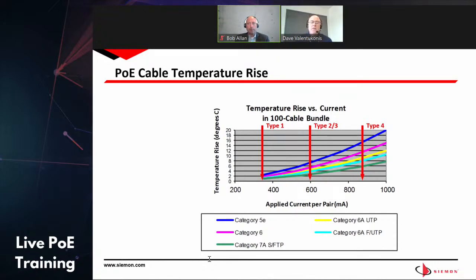Category 5E, for example, is less tolerant of heat because it simply has smaller conductors than the others. As you go up the ladder to category 6, category 6A, category 6A shielded, and even category 7A, which is a fully shielded system, it has the ability to manage that heat dissipation better over the length of that cabling run.